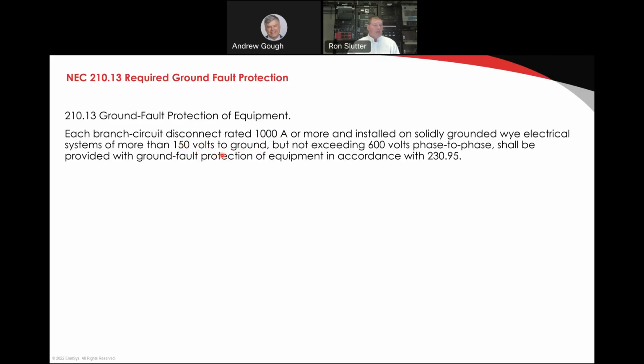So that's expensive and it's required if you have that service. There's no getting around it. And it is because services that are this much ampacity have the ability to do what we call burn down. In other words, a low level fault still has enough capacity to burn the equipment to the ground. So what we do is we put a ground fault protection system so that it can see that low level fault and disconnect. But in a telecom facility, we don't want that to happen. We don't like ground fault because it affects our reliability.